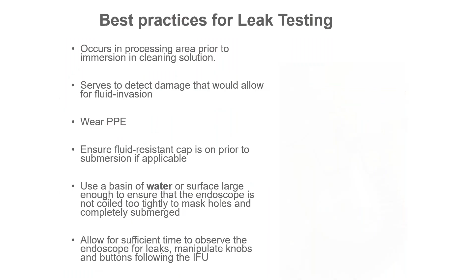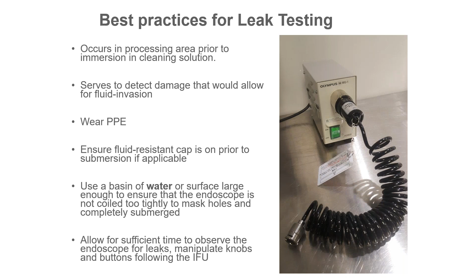One of the issues that we found when I was looking at the cleaning recommended by the manufacturer is that it said to do a leak test, either a dry leak test or, in this case, put it in a basin of water and see if you see bubbles. It was interesting that obviously this is a busy area. So what they said is that usually you plug in the leak tester and listen for that hiss. We've been looking at some of these leak testers, and the hiss really is not a good way of testing them.